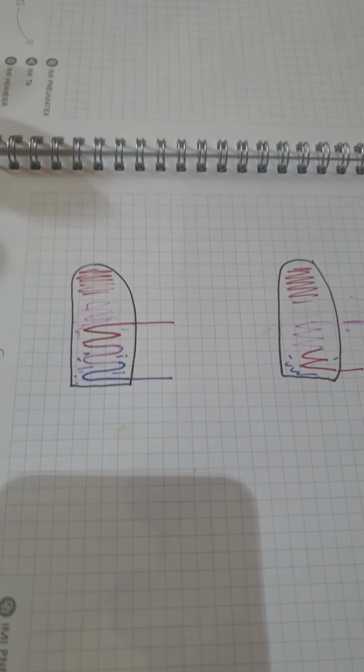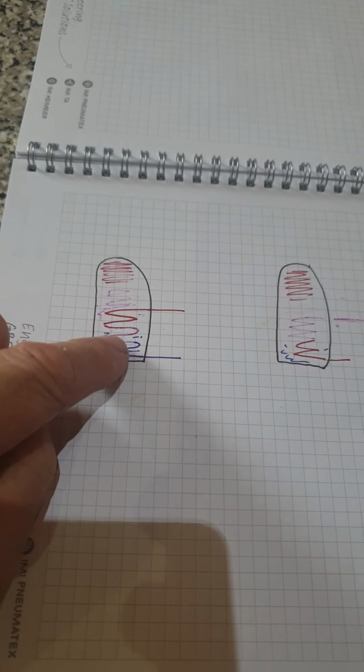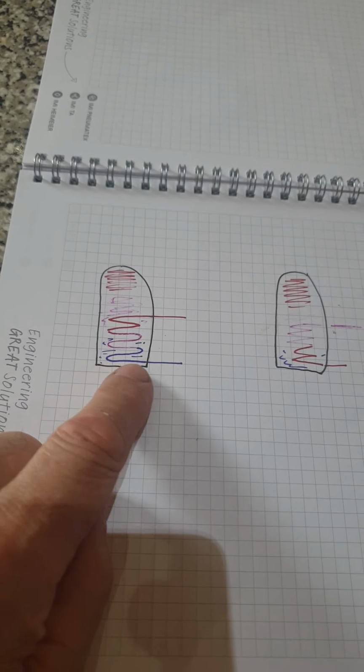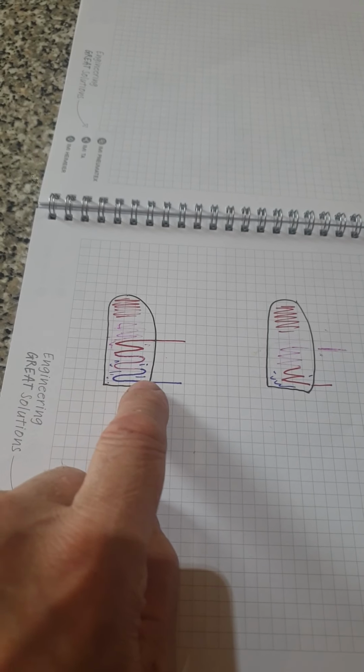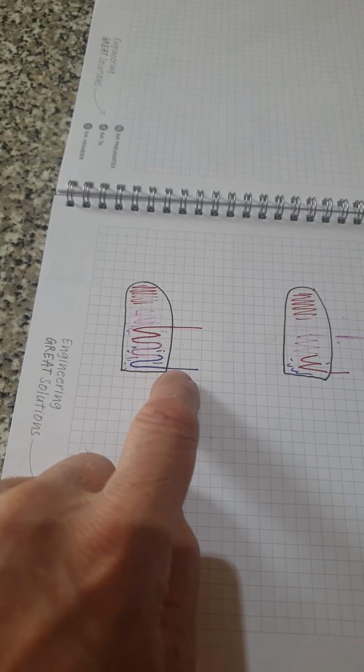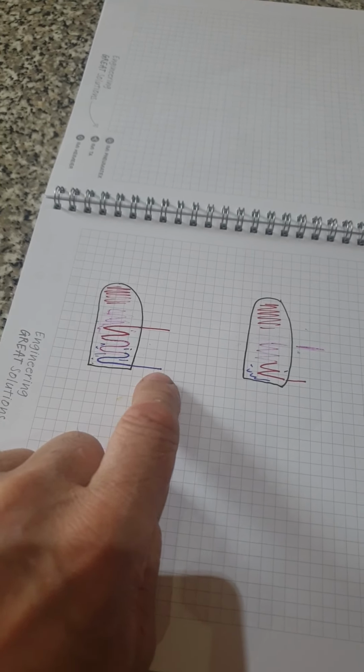But you want to get as much heat out as possible. So basically you want the return to be in the coolest part of the cylinder. And here, obviously, at the bottom of the cylinder, we've got the coolest part, and we can give up as much heat as possible from the coil before it returns back to the boiler.